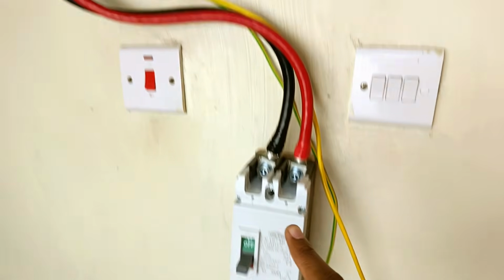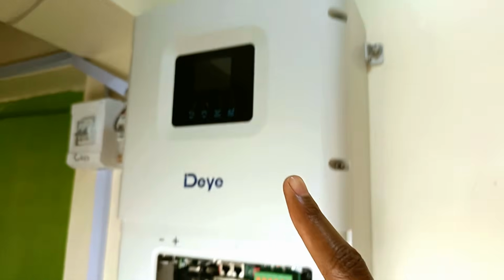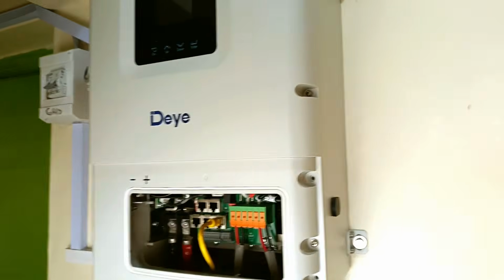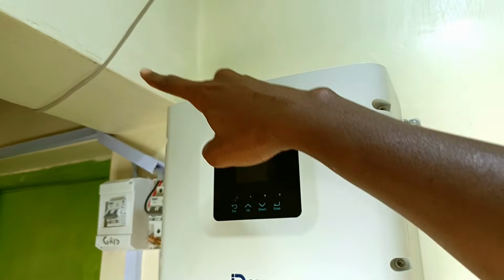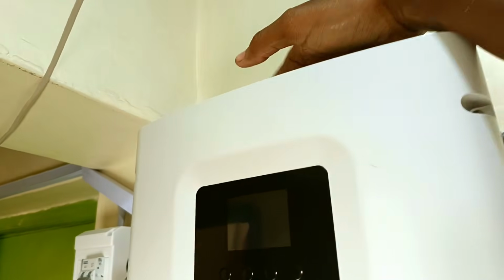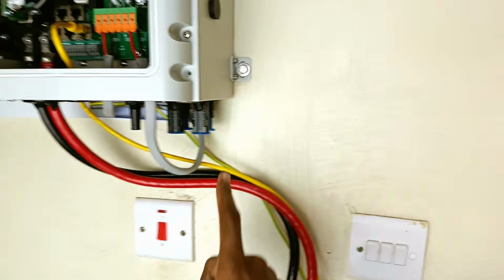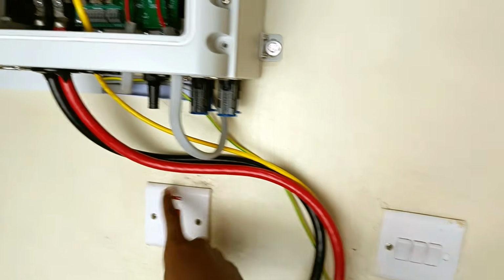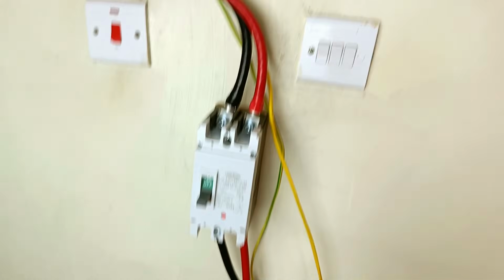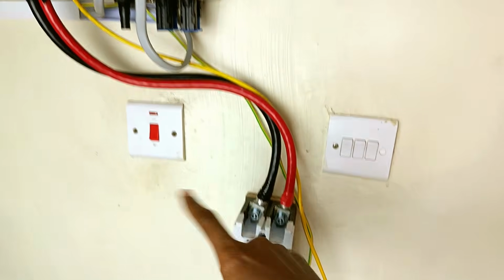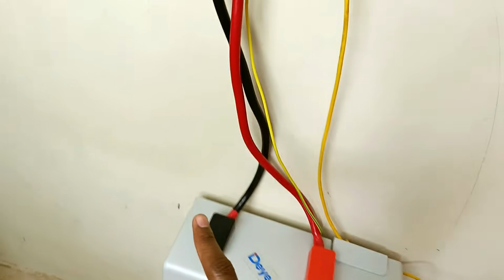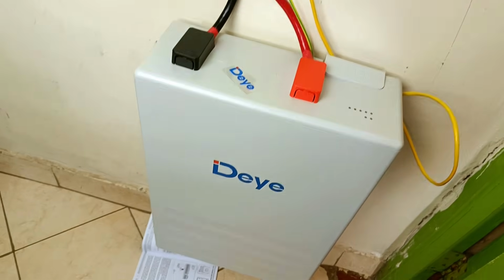This is the position I've chosen for my DC breaker, and as you can tell, the battery is a little bit offset from the inverter. This is the only space I could install these two things. I didn't want to install it below that beam because the exhaust comes from here. I didn't want that going below that. That's why I had to install it here. It was very hard because it's in between two pipes for the water heater and the lights. And because these cables are too thick and I didn't want to coil them, I chose to install the battery offset to this other side.